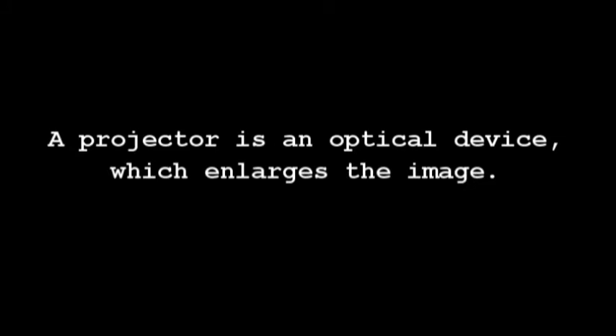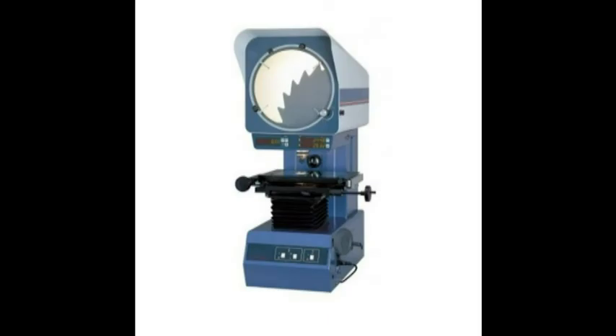Now moving on to the next concept, which is the optical projector. Before entering into the optical projector, let us understand what a projector is: a projector is an optical device which enlarges the image. This is the principle used in the optical projector. Optical projectors are used to check small engineering components with working standards. The components of the optical projector include a light source, condenser lens, projector lens, and screen.